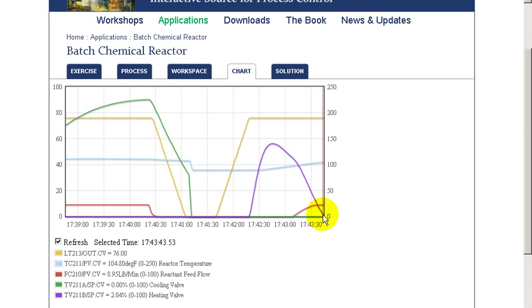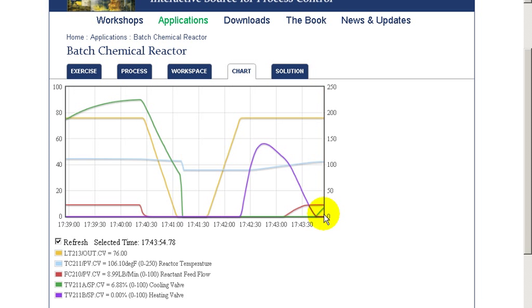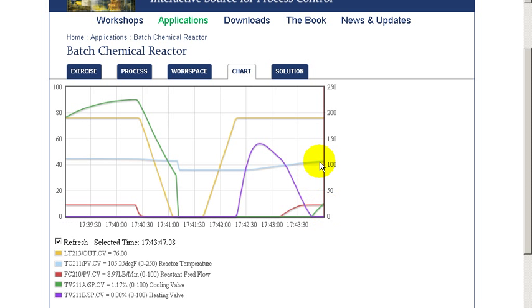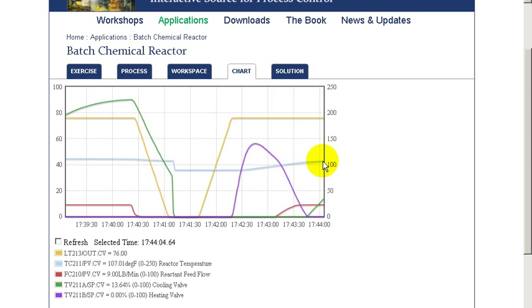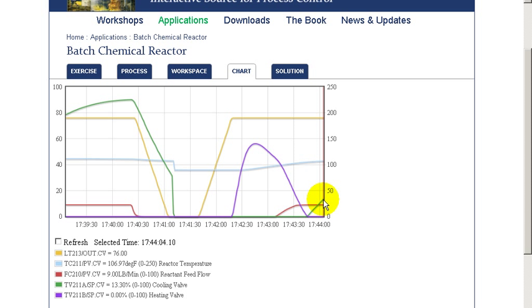You notice a change in the rate of the heat valve being closed as that's added, because this is an exothermic reaction with the second material, so more heat is being generated. At some point, the cooling valve, shown in green here, must open to maintain the temperature of the unit and keep it from exceeding the operator's specified target for temperature.